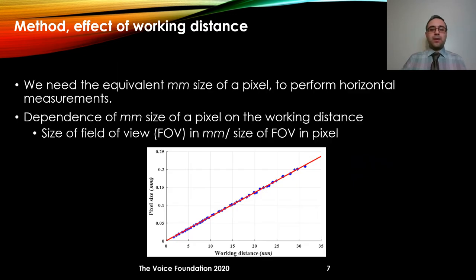We collected a set of benchtop recordings from grid papers at multiple working distances. To perform horizontal measurement, we need to determine the equivalent millimeter size of a pixel. We measured the size of the field of view in millimeters using benchtop recordings, then divided that by the size of the field of view in pixels. The result shows a linear relationship: as working distance increases, the pixel size also increases.